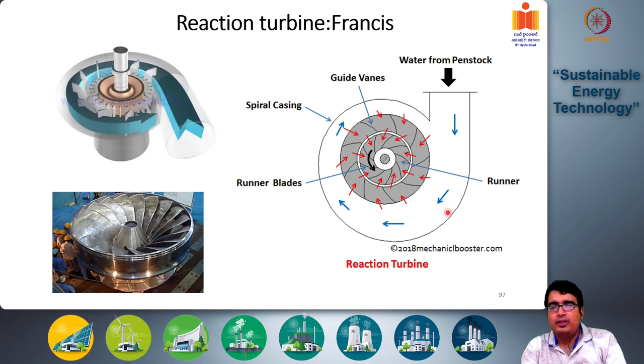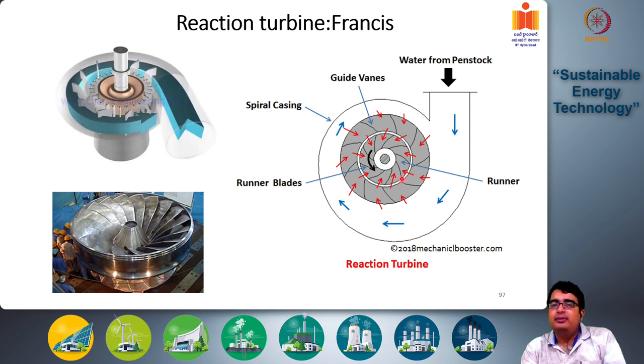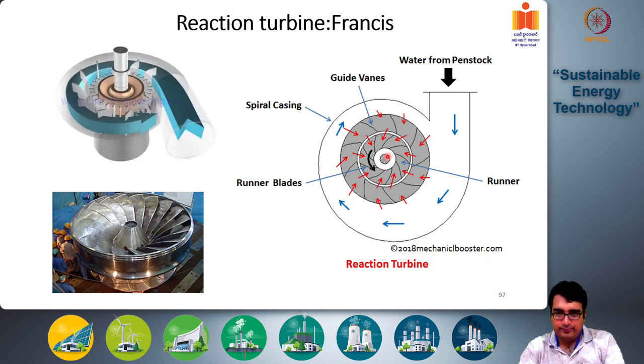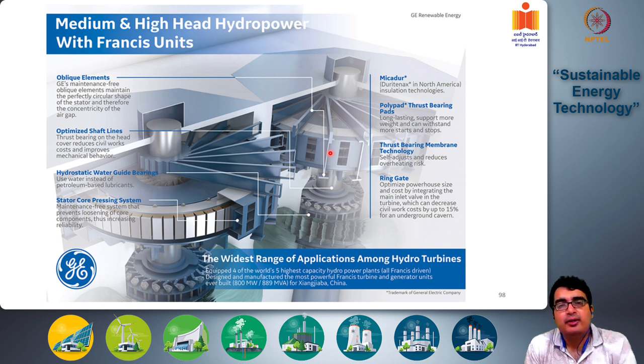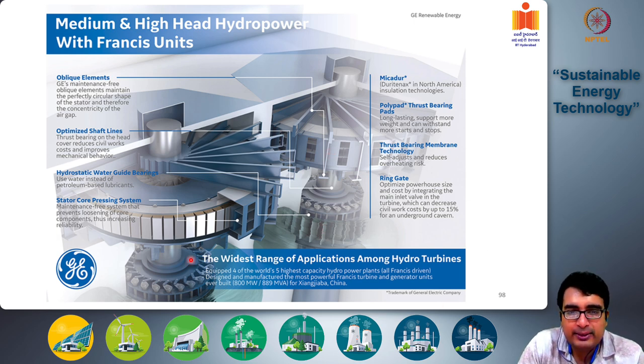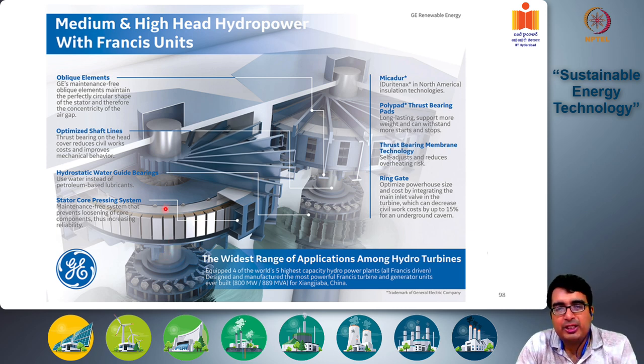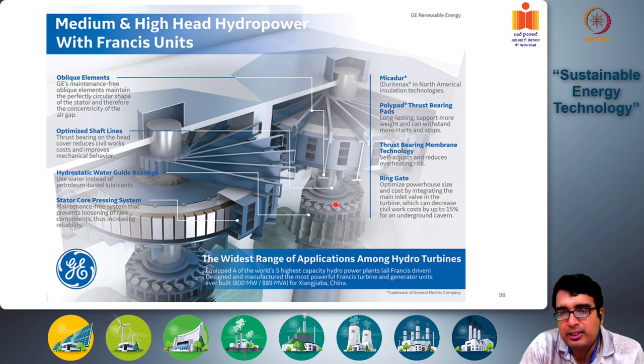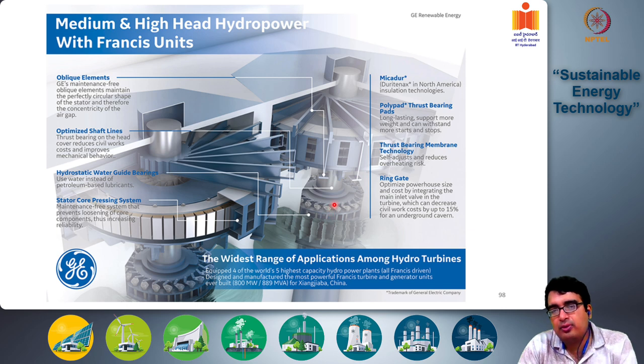The outer casing houses the stators, also called guide vanes, which are connected to the spiral casing outside and direct the water into the rotors. The rotors then rotate and generate kinetic energy in the turbine shaft, which is eventually converted to electrical energy. The flow of water is shown by the red arrows. This is a GE version of a medium and high head Francis unit — the turbine section connects to the generator part, and you can see the stator and rotor blades clearly.